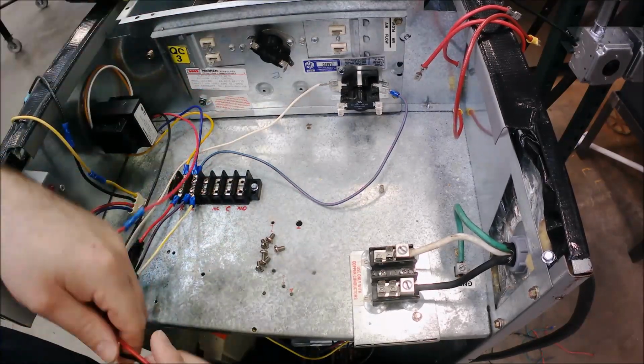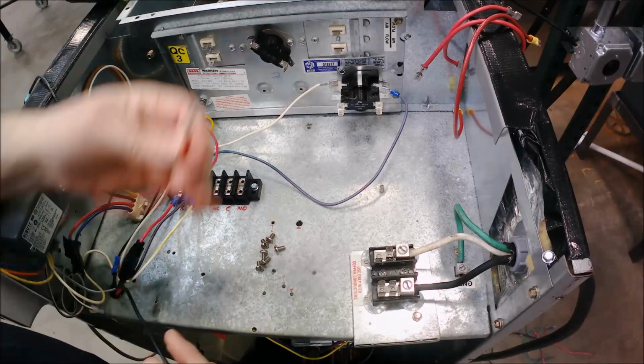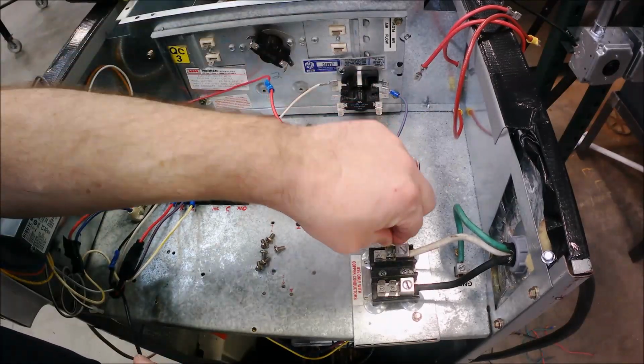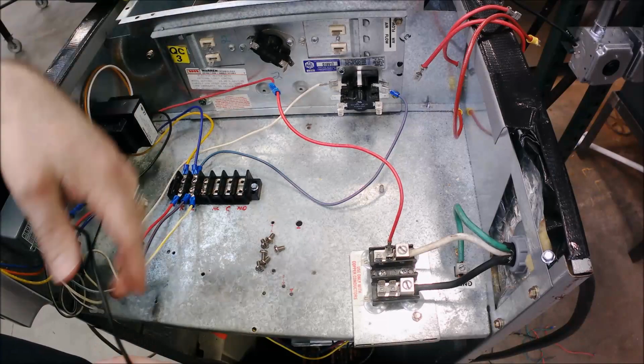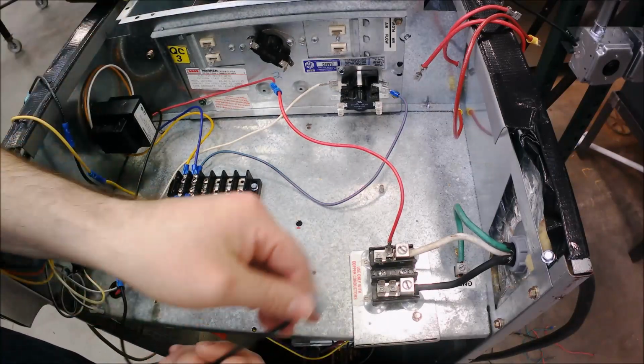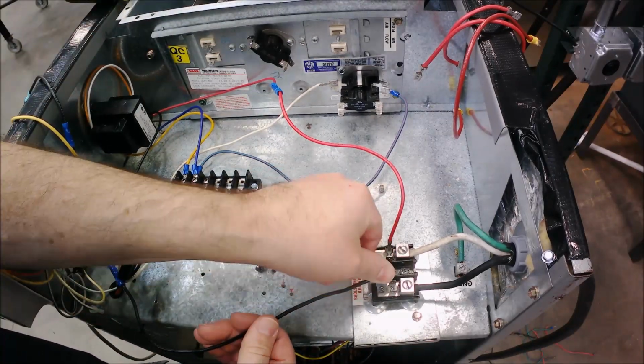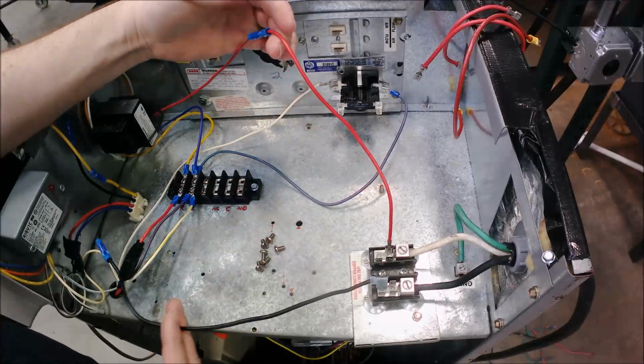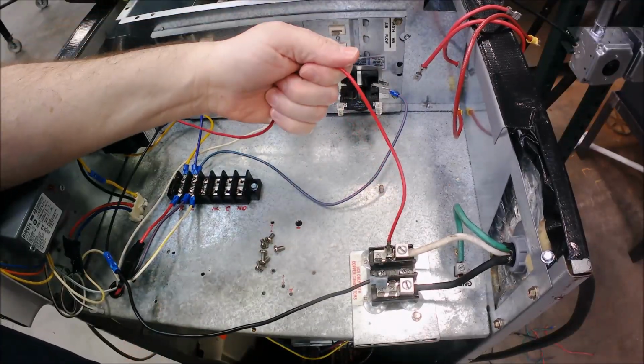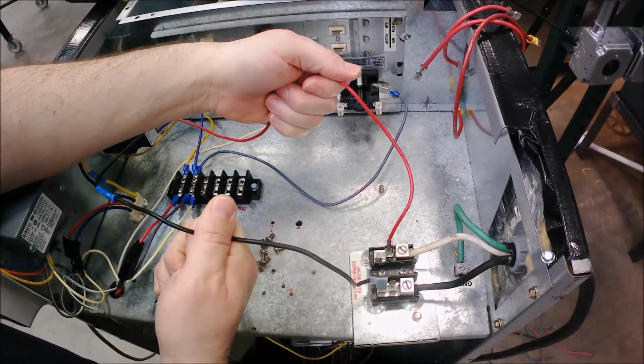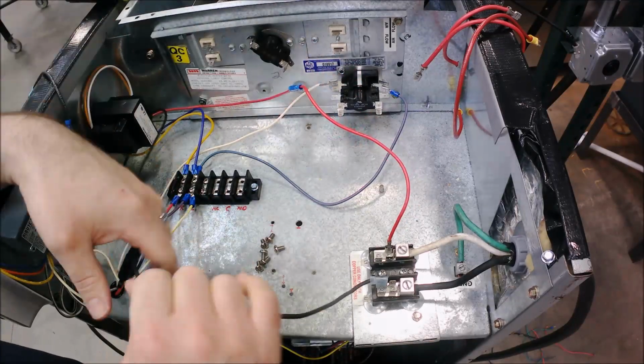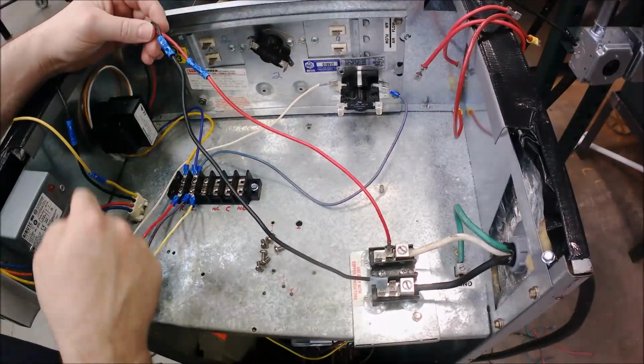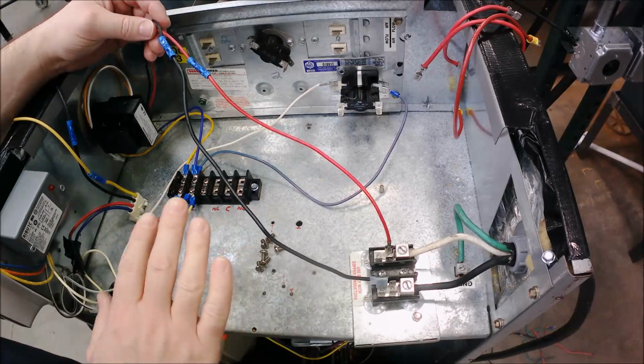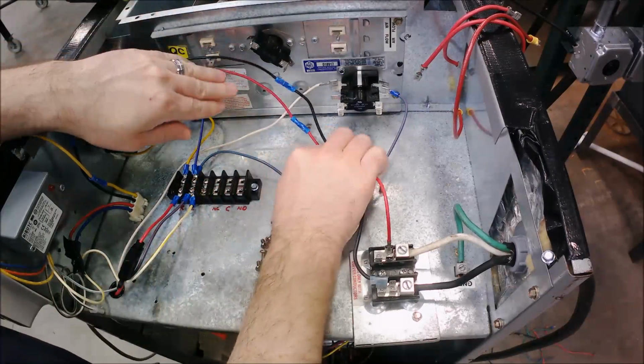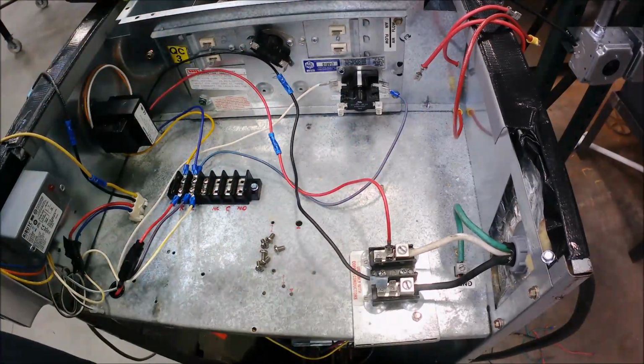So I'm going to run L1 into the transformer, and this is going to be my L2, this black one right here. And now that I call it that way, this is always L1 and this is always L2. So transformer's out of the way, we have the high voltage, that's going to give us the low voltage, all that's done. Now let's look at a heat strip.